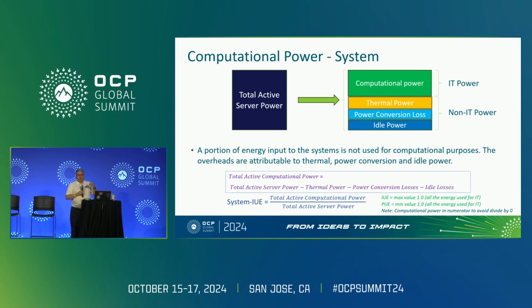So while PUE was looking at the data center level, it was assigning anything going to the compute infrastructure - meaning if it went to the rack, or the rack of IT gear - as an efficient use of power, as opposed to going to the chillers, air handlers, or air conditioner units, which was considered the inefficient use.